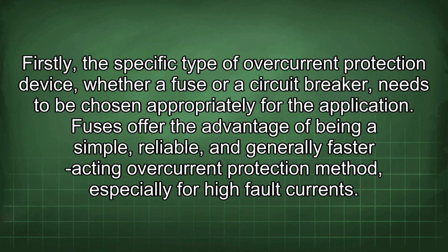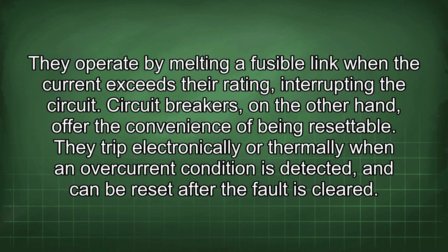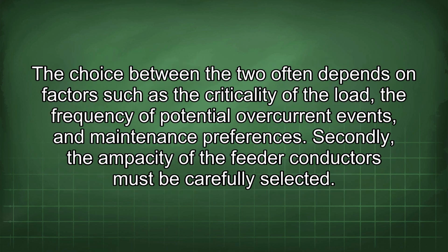Firstly, the specific type of overcurrent protection device, whether a fuse or a circuit breaker, needs to be chosen appropriately for the application. Fuses offer the advantage of being a simple, reliable, and generally faster acting overcurrent protection method, especially for high fault currents. They operate by melting a fusible link when the current exceeds their rating, interrupting the circuit. Circuit breakers, on the other hand, offer the convenience of being resettable. They trip electronically or thermally when an overcurrent condition is detected and can be reset after the fault is cleared. The choice between the two often depends on factors such as the criticality of the load, the frequency of potential overcurrent events, and maintenance preferences.